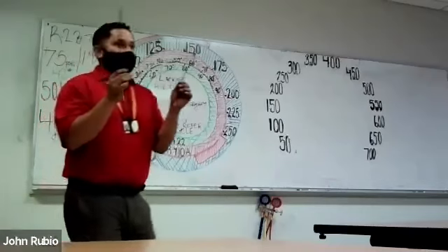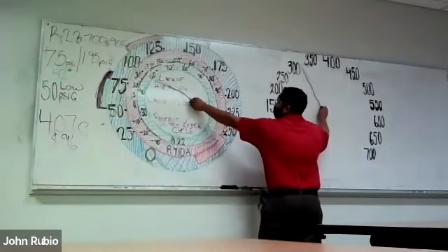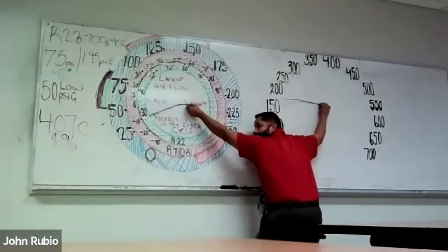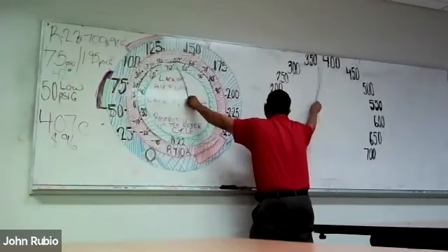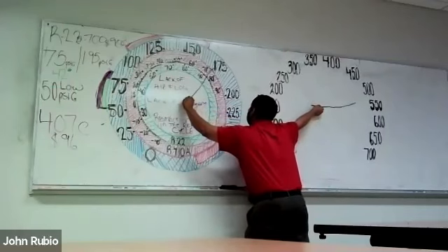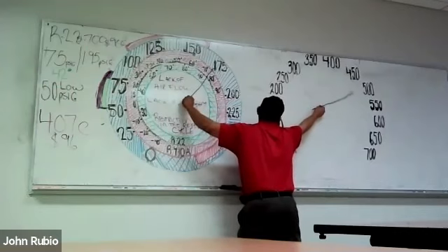The very congruency of your needles will tell you so much. If we truly are low, my needles will be low. If I truly am overcharged, both of my needles will show overcharged. They'll both be in somewhat of congruency until they get so overcharged it slams itself shut.